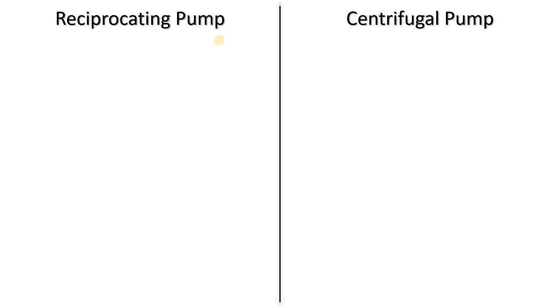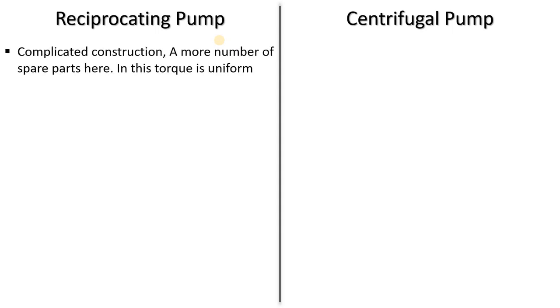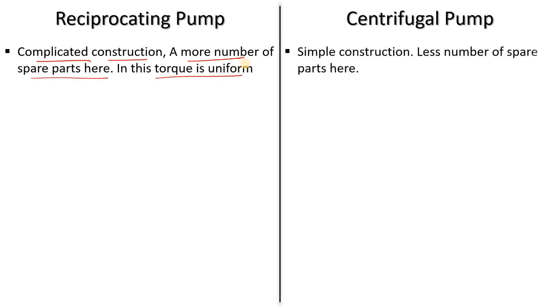The reciprocating pump is complicated in construction with more spare parts — piston, chamber, crank rod, crankcase — while the centrifugal pump is simple with mainly just an impeller and casing, and fewer spare parts. The torque in a centrifugal pump is uniform, while in a reciprocating pump it is not.